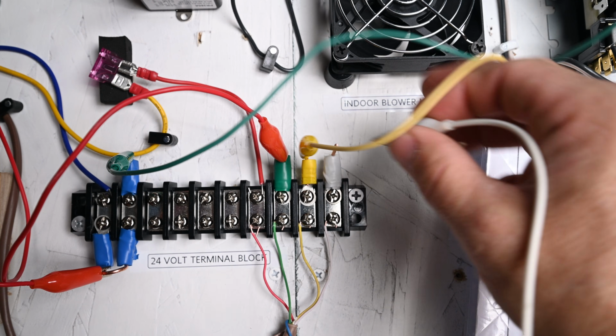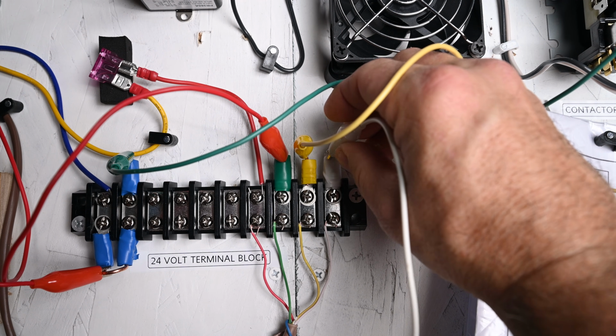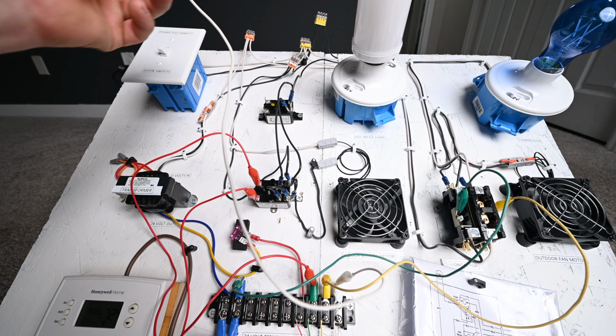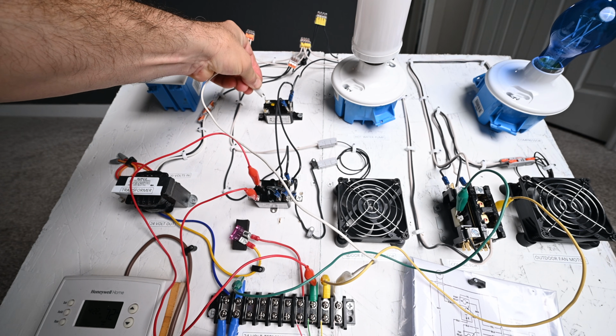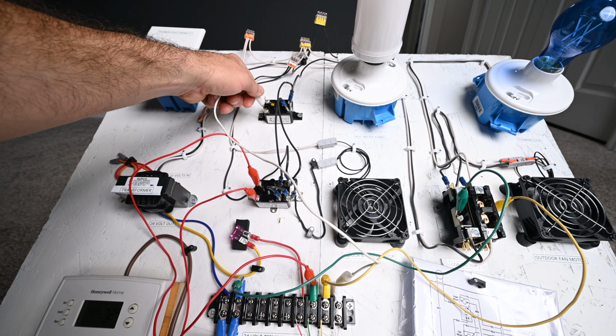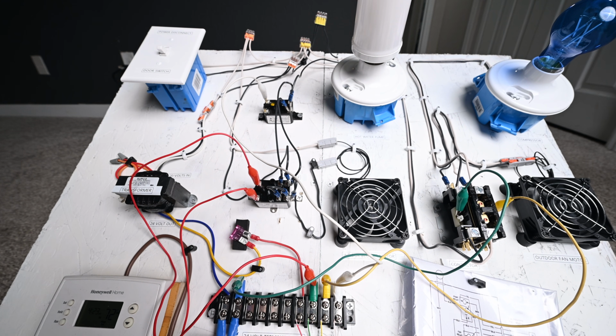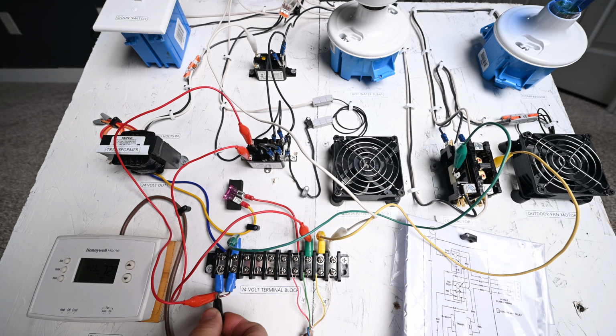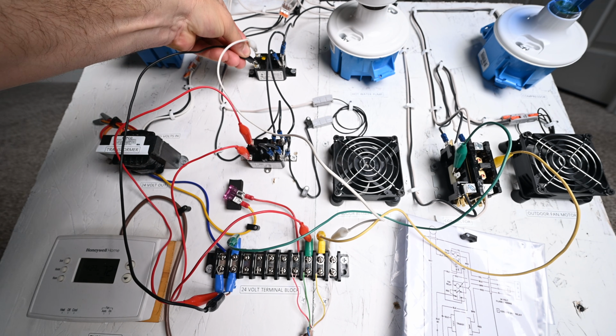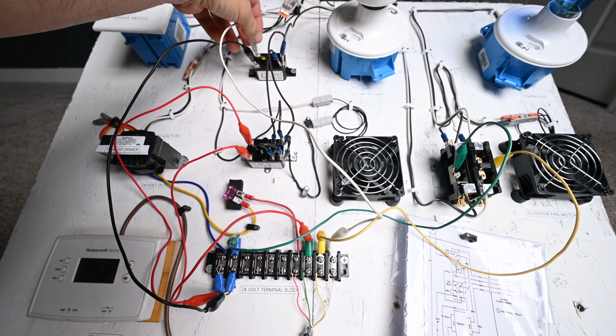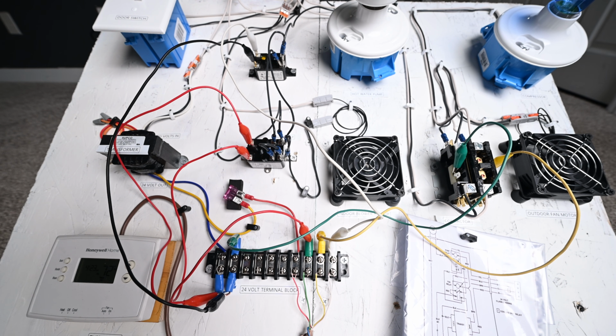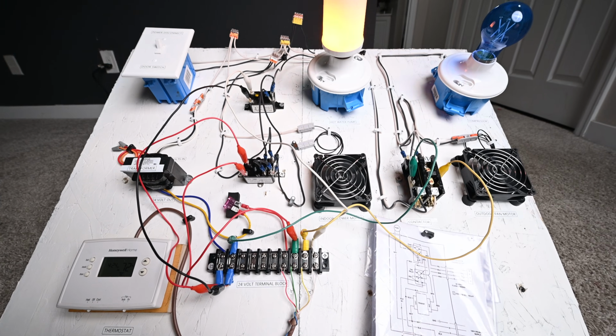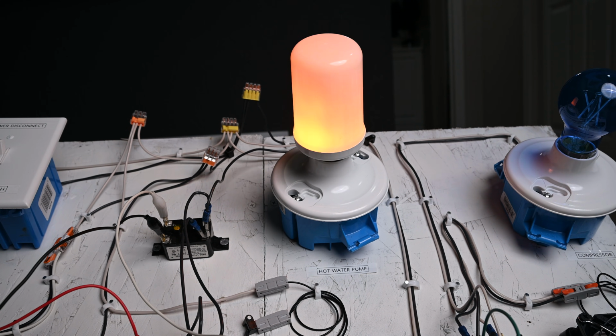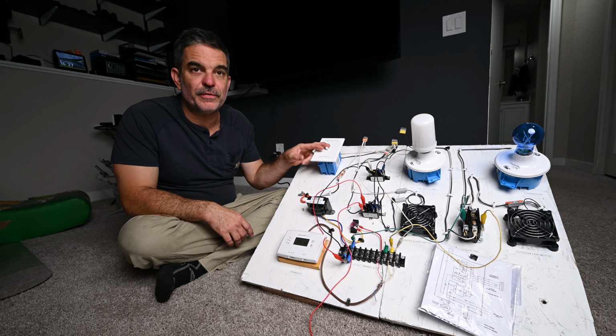Our white wire is going to be the power for our heat, our 24 volt power for heat. Hook one clip up to the white wire, while this other end goes to the pump relay coil. Doesn't matter which terminal, this one or this one. Just don't hook it up to a high voltage terminal. And what do you think we're going to hook up next? You got it. We're going to hook up the common, because the circuit will not be complete without a common. Got plenty of room on my common bar that I made. And then this is going to go to the other end of the coil. Now we don't want those to touch, or else that fuse is going to pop. Turning on the power now. And our indoor fan came on, and our heater is now on. And that is some very basic low voltage configurations in HVAC.